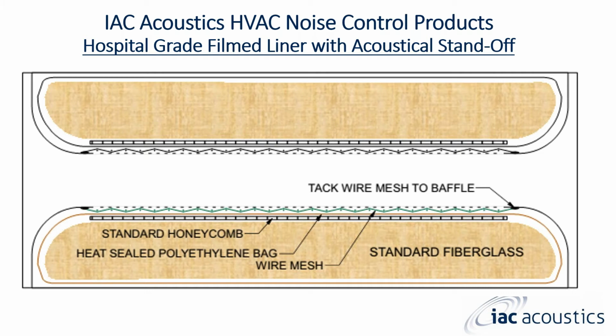So you have the two baffles, and inside each of the baffles, you have the solid noses on the ends. You have your perforated. Behind that, you will then have your wire mesh. Now that helps to separate what is inside the heat-sealed polyethylene bag. Inside that, you will have your acoustical standoff, which is a standard honeycomb type mesh material, and your standard fiberglass. Again, all of that is within the 100% heat-sealed polyethylene bag behind the wire mesh, which is then behind the perforated material.